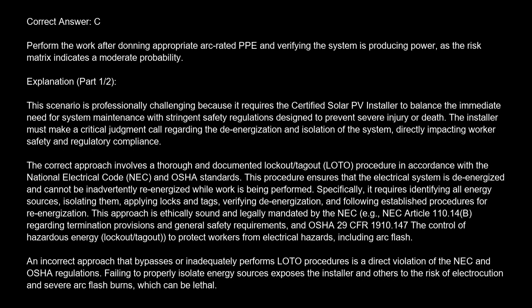Installer must make a critical judgment call regarding the de-energization and isolation of the system, directly impacting worker safety and regulatory compliance. The correct approach involves a thorough and documented lockout/tagout (LOTO) procedure in accordance with the National Electrical Code (NEC) and OSHA standards. This procedure ensures that the electrical system is de-energized and cannot be inadvertently re-energized while work is being performed.